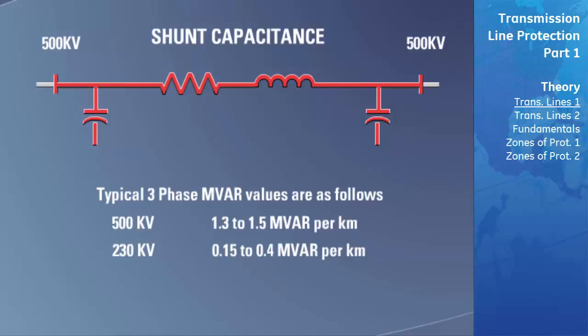Shunt capacitance occurs between the transmission lines and the ground. This capacitance counterbalances some of the inductance by adding leading MVARs on the line and helps bring the current and voltage back to unity power factor. Caution needs to be taken with high voltage potentials. Due to the Ferranti effect, the shunt capacitance on the line can become so large that the voltage on the far end of the line can rise higher than the normal line potential.